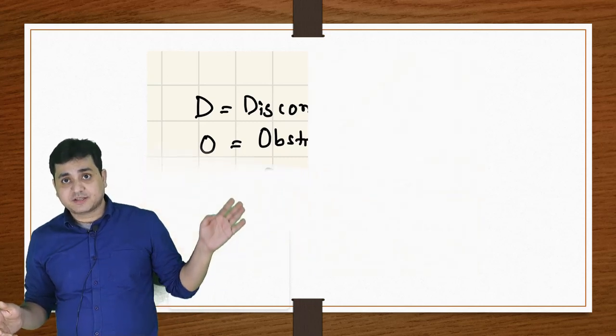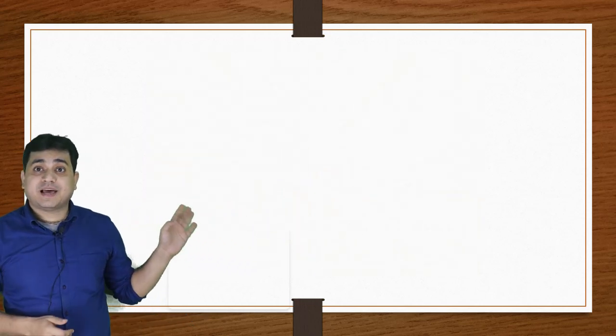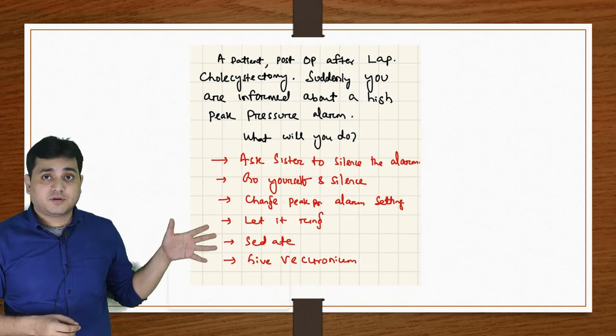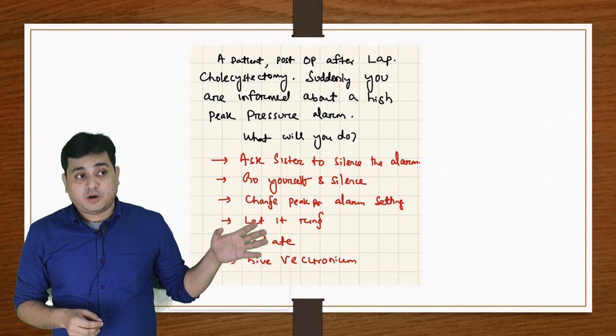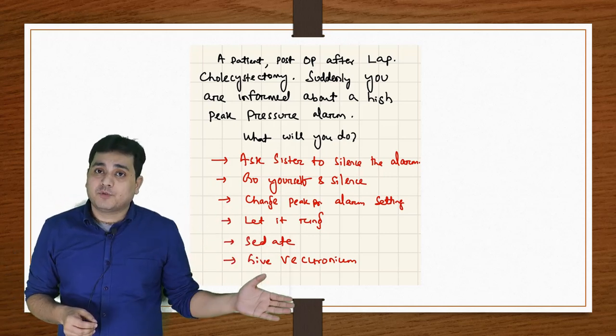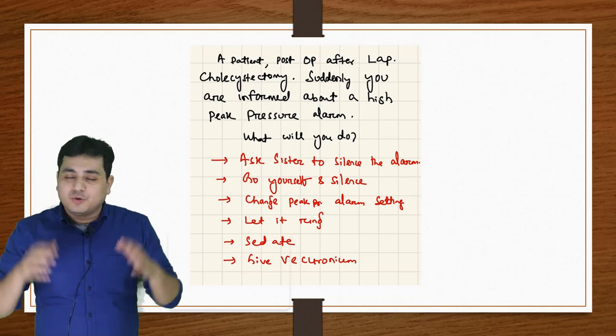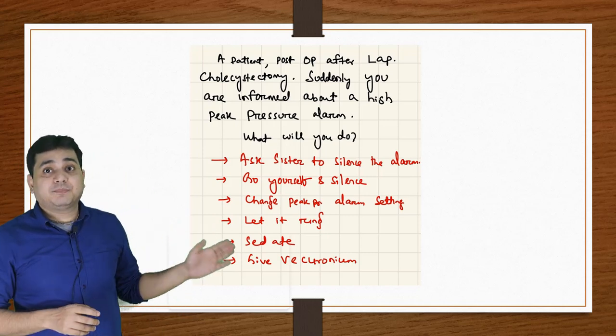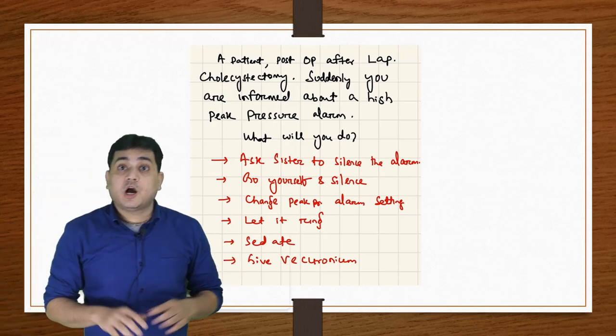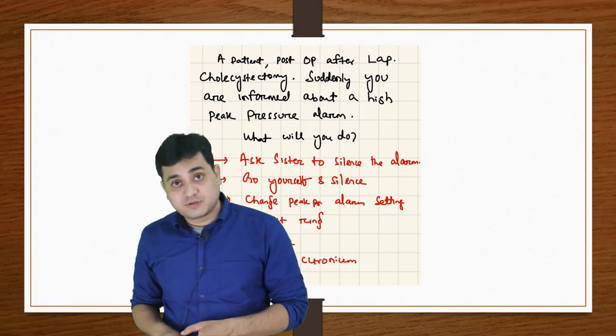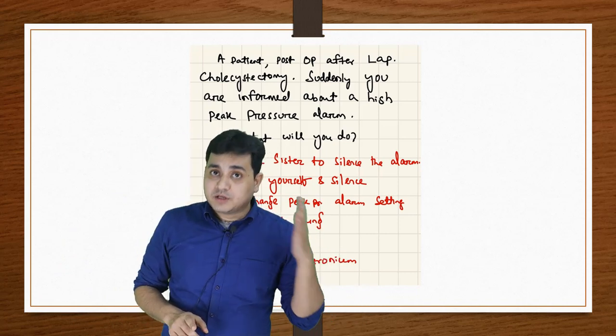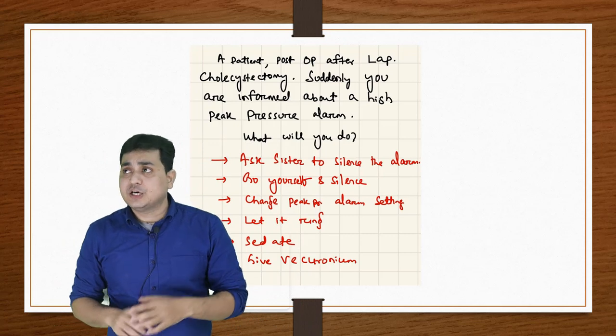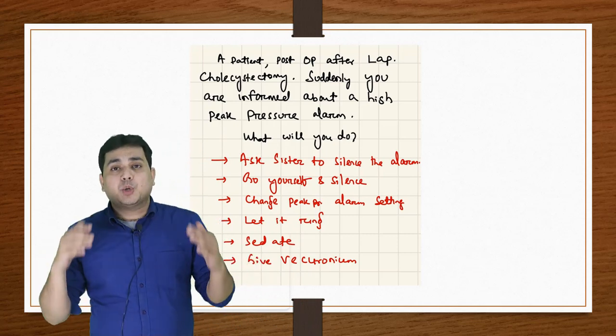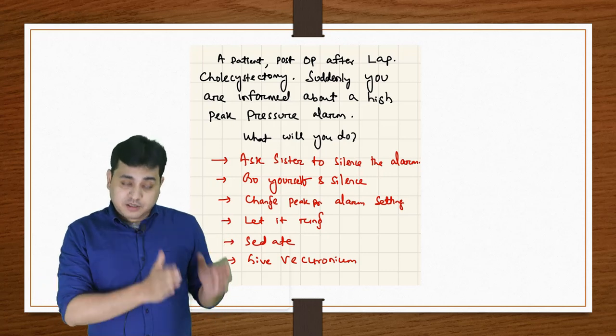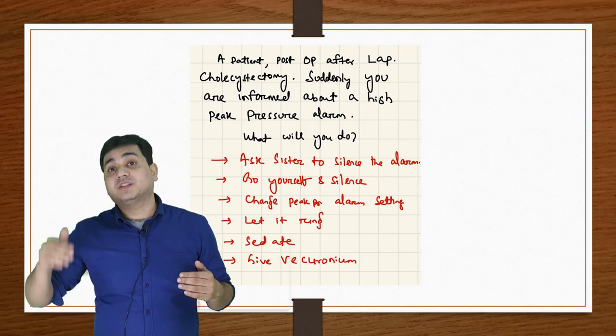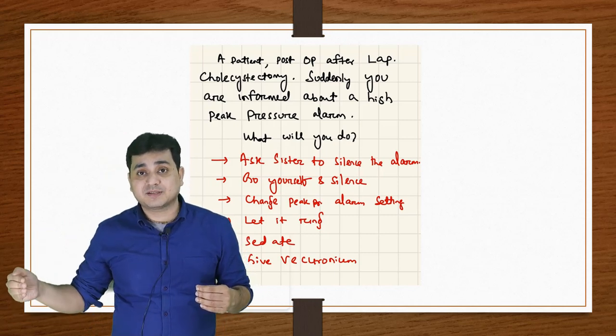Now my question is: read this case with a peak airway pressure alarm, and we have a few options. What is the correct option? Either you call the sister and tell her to silence the alarm, or you go yourself and silence the alarm, or you let it ring and do nothing, or you sedate the patient, or you give vecuronium. None of these answers is correct. The correct approach, as I told you earlier, is to go to the patient, look, listen and feel, check the parameters, go to the ventilator, check the airway pressure, and divide the problem into a resistance or compliance problem or another systemic problem like pulmonary embolism or systemic sepsis. Then deal accordingly.